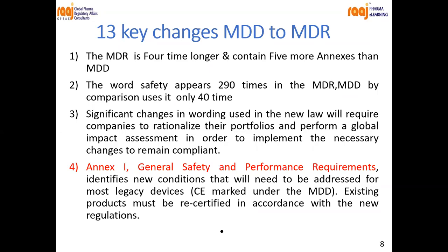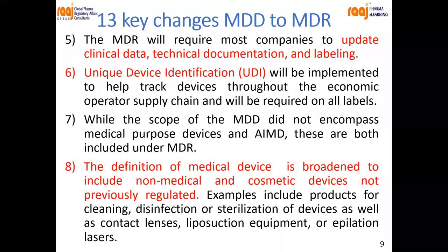So as I said earlier, all the medical devices which are already in the market have to be recertified for the CE mark. The CE mark is mainly used in the EU market, and we discussed during the last lecture how the CE mark is done. Then the fifth change is the MDR will require most companies to update clinical data, technical documentation, and labeling.